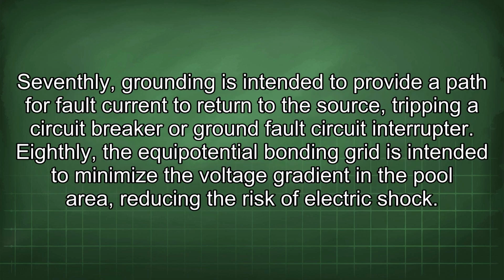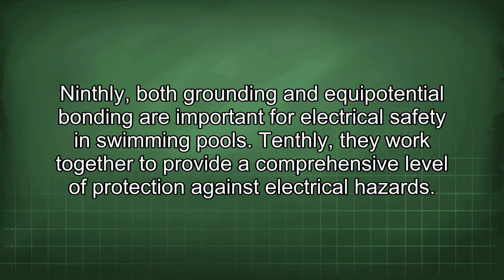Seventhly, grounding is intended to provide a path for fault current to return to the source, tripping a circuit breaker or ground fault circuit interrupter. Eighthly, the equipotential bonding grid is intended to minimize the voltage gradient in the pool area, reducing the risk of electric shock. Ninthly, both grounding and equipotential bonding are important for electrical safety in swimming pools. Tenthly, they work together to provide a comprehensive level of protection against electrical hazards.